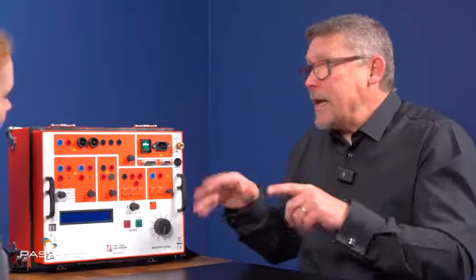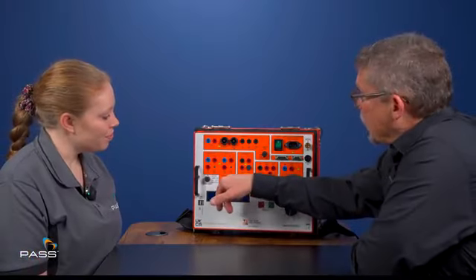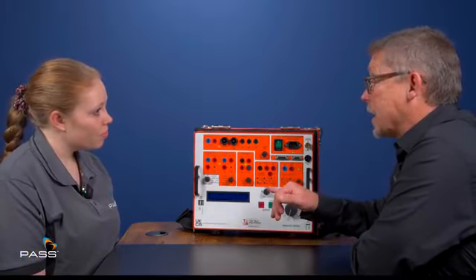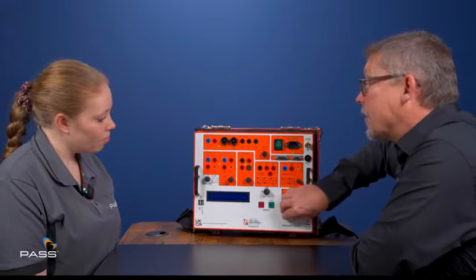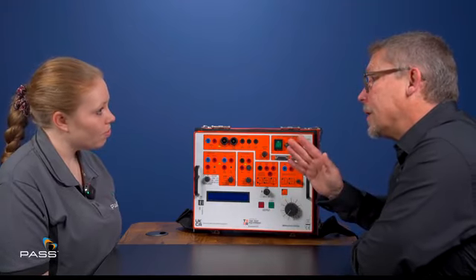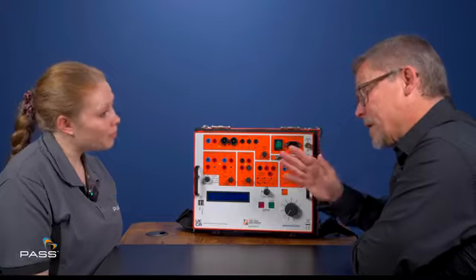We have pulse mode. Now, if we're doing, for example, a thermal relay, if you spend a lot of time setting them up, you're going to warm them up before you even start. So what we do here is we give a pulsed output, which is 200 milliseconds, and we can then set the current without warming up the relay that we're testing.